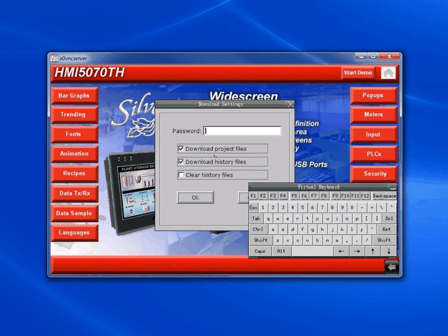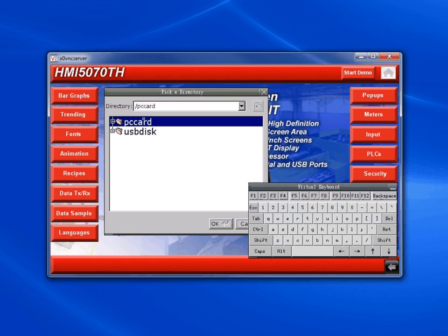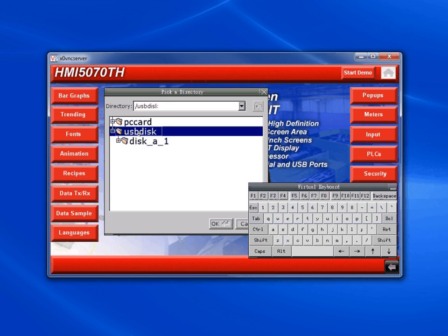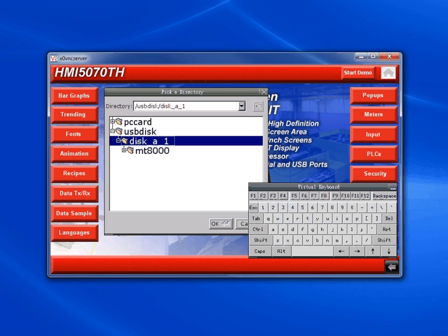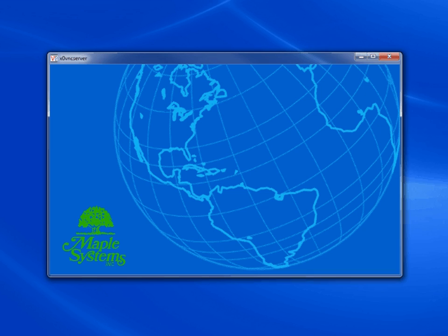Click the download button. Enter the download password and click OK. In the 'Pick a Directory' window, select the file that is right above the MT8000 file — in this case, disk A1 — then click OK. The project will download into the HMI and the HMI will restart. When the HMI comes back online it will load your project.